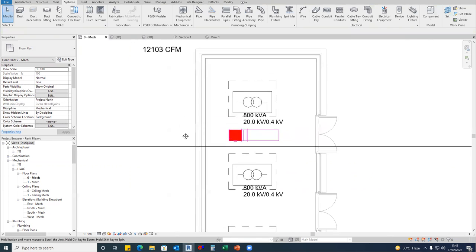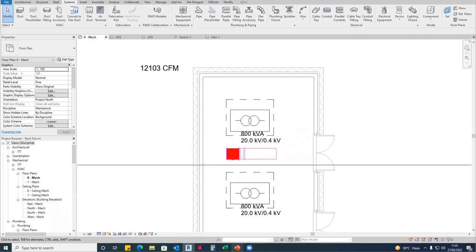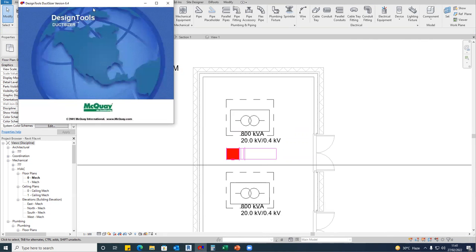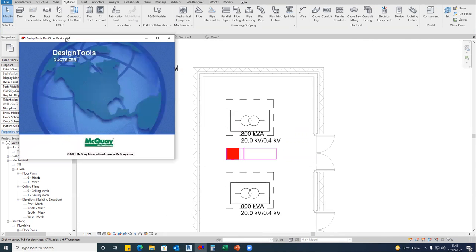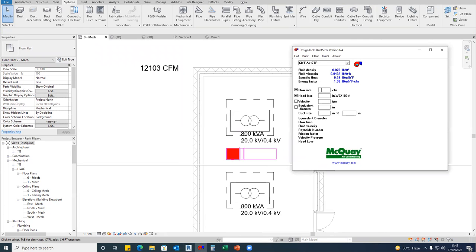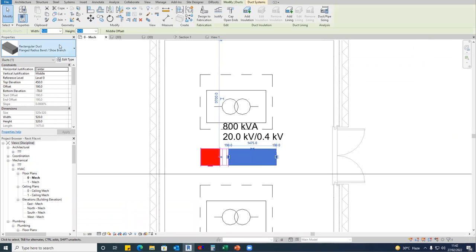Okay, now for this CFM, what is the duct size? Let me open this one. The CFM is 12,103. Friction, I'll take 0.1. And say 30, it is 36. 32 by 33, so I'll take 32 by 34 inches, that is 850 by 800.